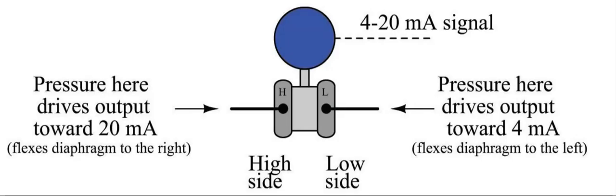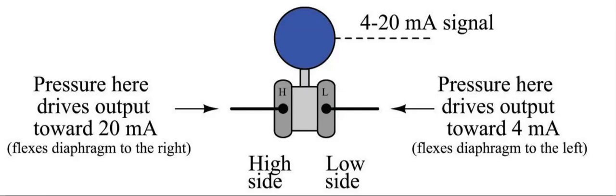Differential pressure transmitters give an electrical signal output, normally in a current range of 4 to 20 milliamps, which is an analog signal very common in process control. They can have digital outputs in the form of HART protocol or Foundation Fieldbus protocol, but for the vast majority of systems in industry today they still use a 4 to 20 milliamp electrical current output.